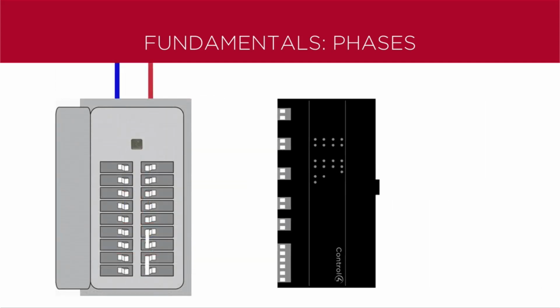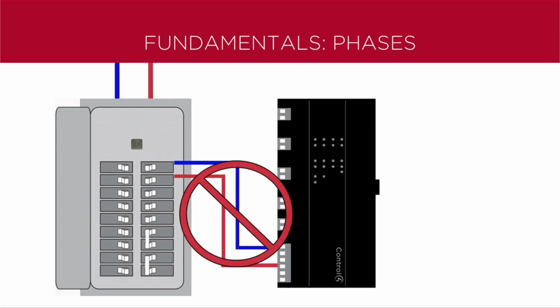When connecting a dimmer module to a fuse box, lines 1 and 2 need to be connected to the same phase. If they are connected to different phases, the lights could flicker, and other detrimental side effects could include white noise on your TVs and poorly functioning electronic devices. Coordinate with the electrician to ensure proper design and connections to the module.